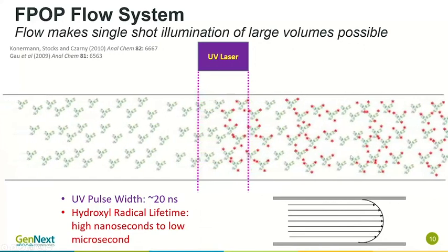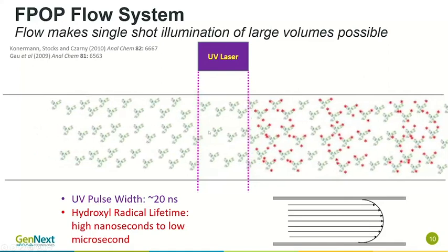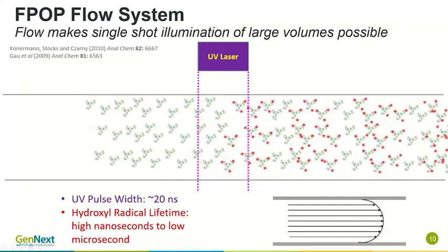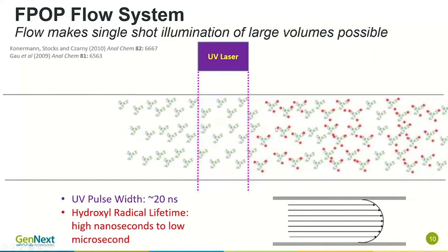Why do we have this region that's not illuminated, called the exclusion volume? The reason is that your proteins in the capillary don't exactly move like this. This is plug flow, where all parts of the capillary are moving at the same speed. That's not how capillaries work.